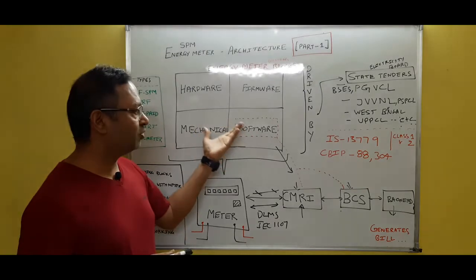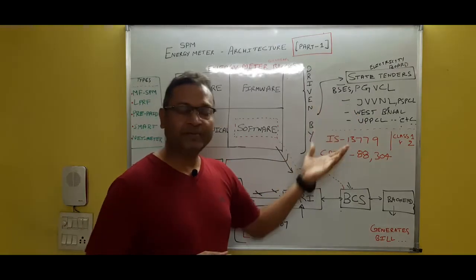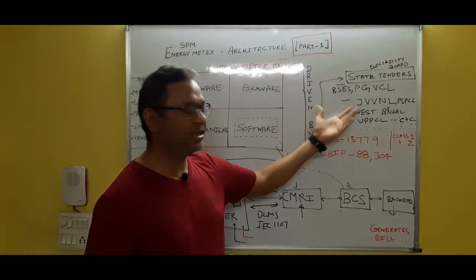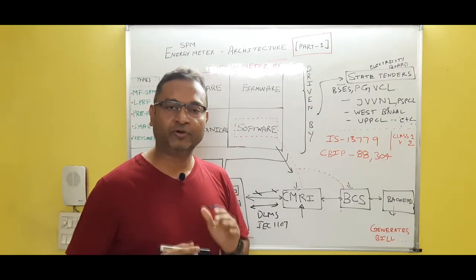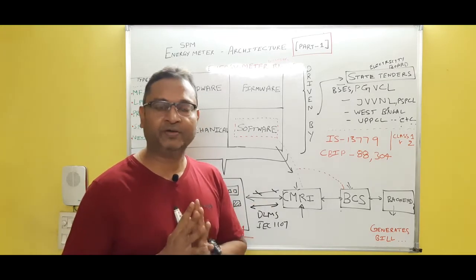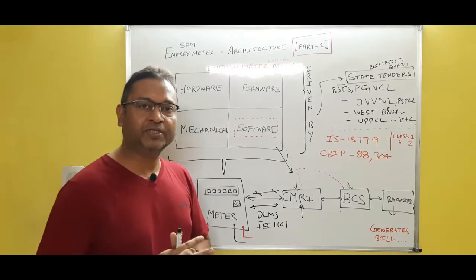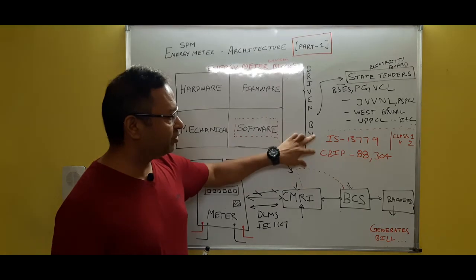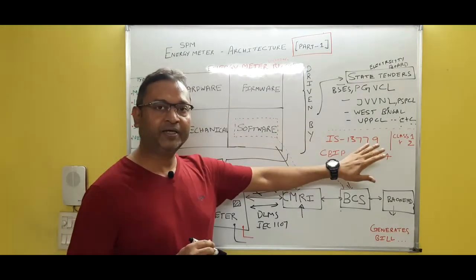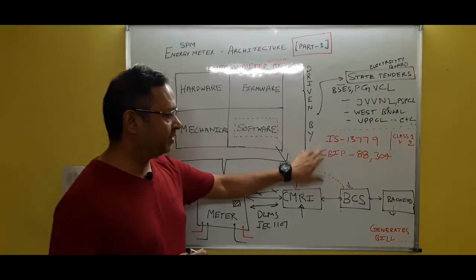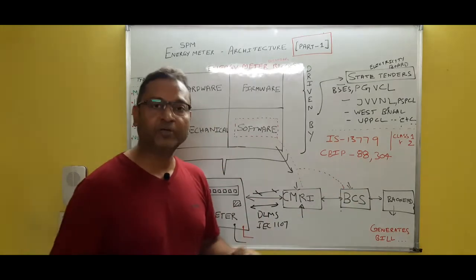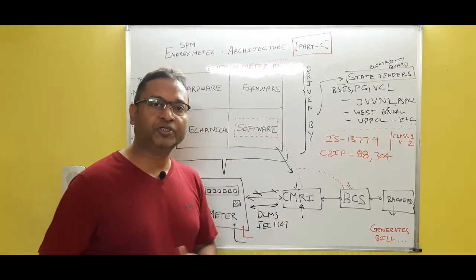So let's discuss about this. The overall design of all these four blocks is driven by our state tenders. State tenders I mean to say that there are a couple of names like BSES tender, PGVCL like Gujarat, and JVVNL, etc. For example, West Bengal, UP tender, and etc. Here what I mean to say is that every state floats a tender, and as per that tender, your display parameters may be different, your mechanical casing may be different, your nameplate may be different. But a few things remain constant, which means that every tender says that you need to follow this particular specification IS 13779. This is for class 1 and class 2 meters and generally applied to your single phase meters. And there is one more body named as CBIP, and in this report number 88 and 304 have some particular technical specifications, and as per that, some features need to be implemented into the meter.